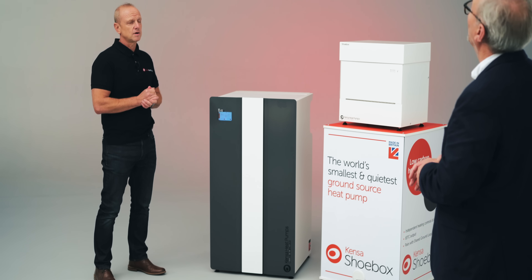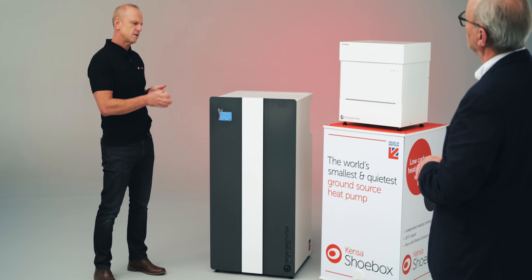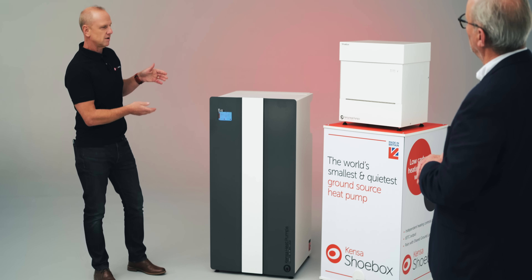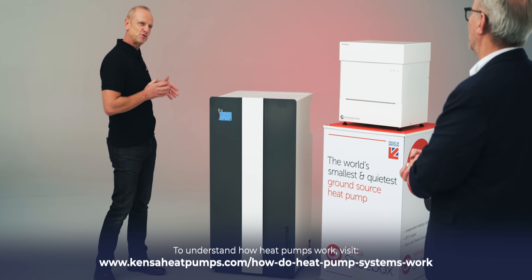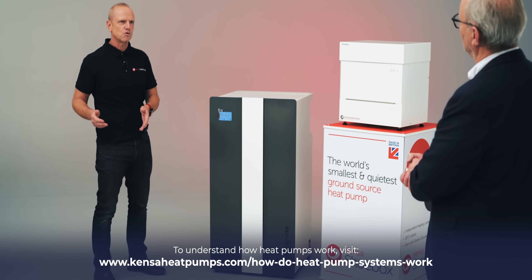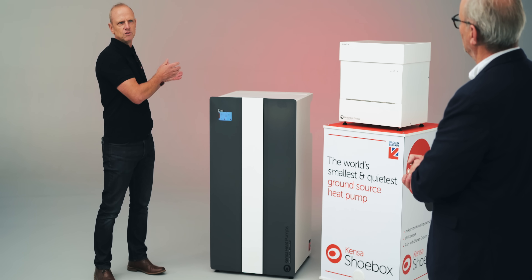The noise — I'm just trying to imagine where it's coming from, presumably that is the pump as it were? The noise is actually the compressor. Inside a heat pump we have a couple of components: a couple of pumps — a ground side pump and a load side pump — and essentially a compressor, which is the noisy bit. Is it a similar overall idea to something you'd have in the back of a refrigerator? Absolutely, on a bigger scale. We're not taking the heat out of food and pushing it out the back of a fridge — we're essentially taking energy from the ground or water, wherever it may be, and transferring it into usable energy inside the heat pump and putting it into a distribution system.